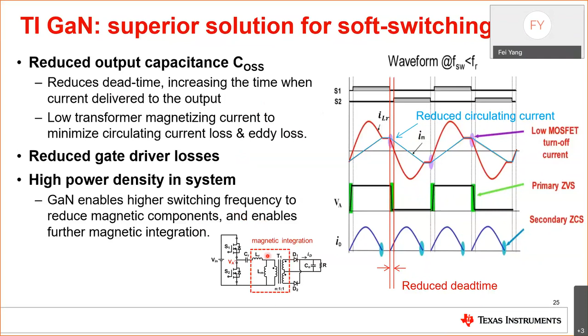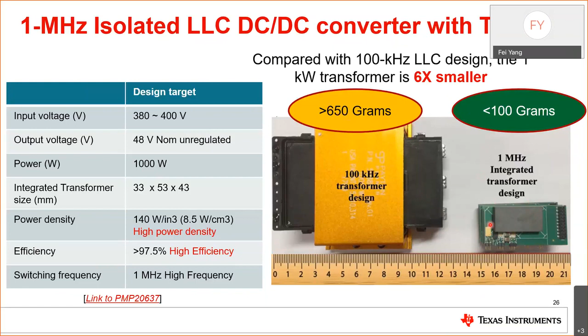Here I'm showing one of our reference designs on the LLC DC-DC stage. It's a 1 kilowatt LLC design, and we're comparing the transformer sizes of our TI GaN design, which is operating at 1 megahertz, versus a silicon super junction design operating at 100 kilohertz. First of all, you see a significant size reduction in the transformer design, and in terms of weight, a reduction from more than 650 grams to less than 100 grams. That validates a high power density design on the DC-DC stage with TI GaN.